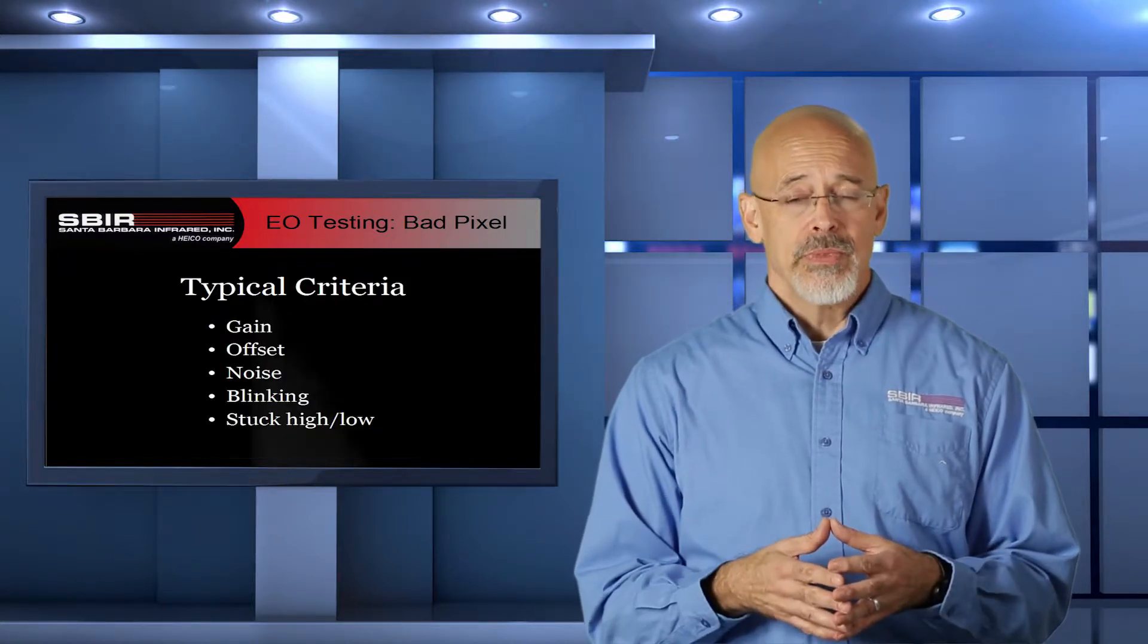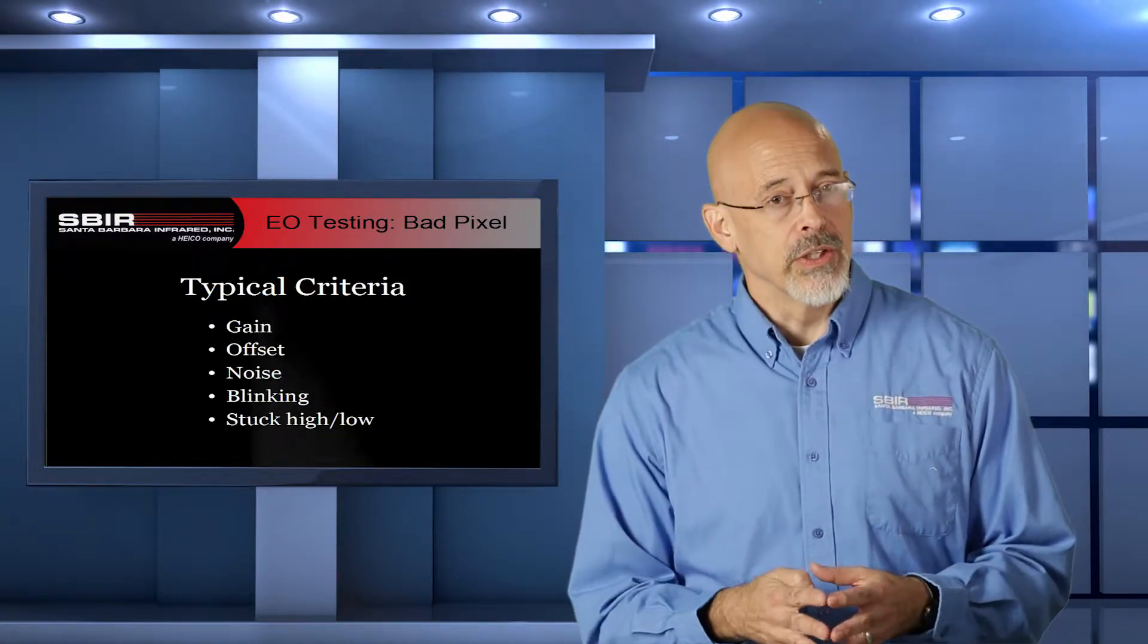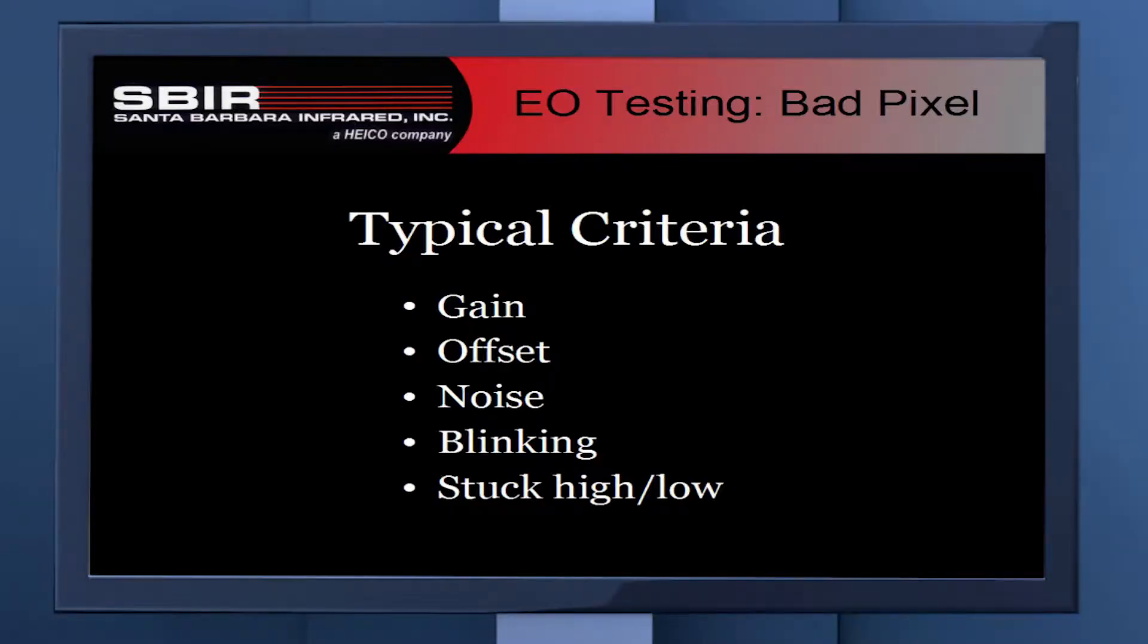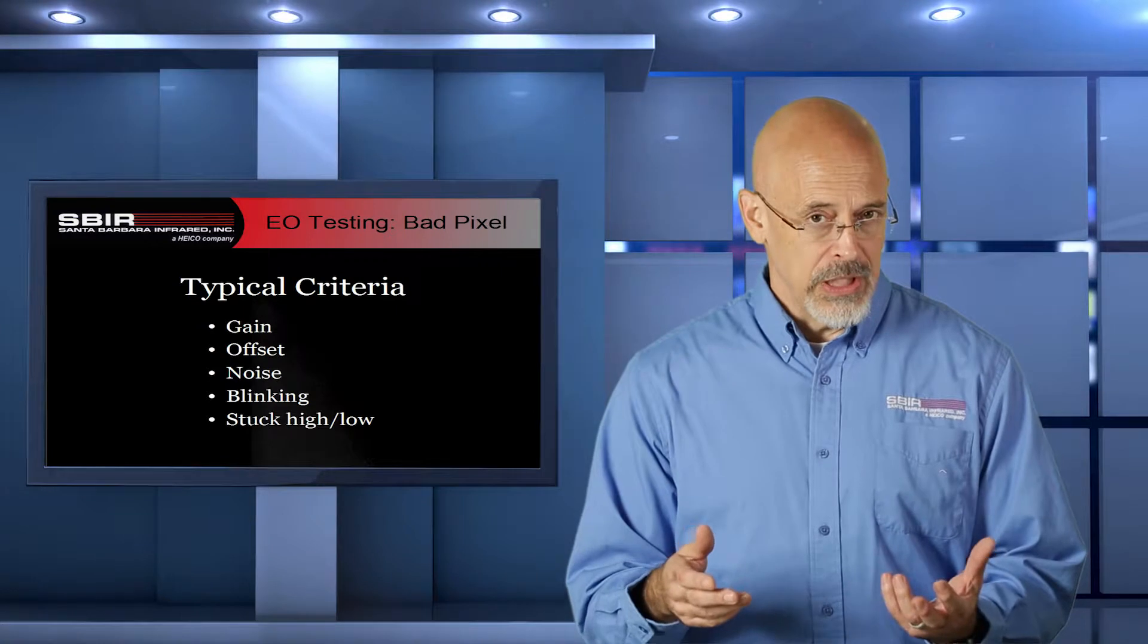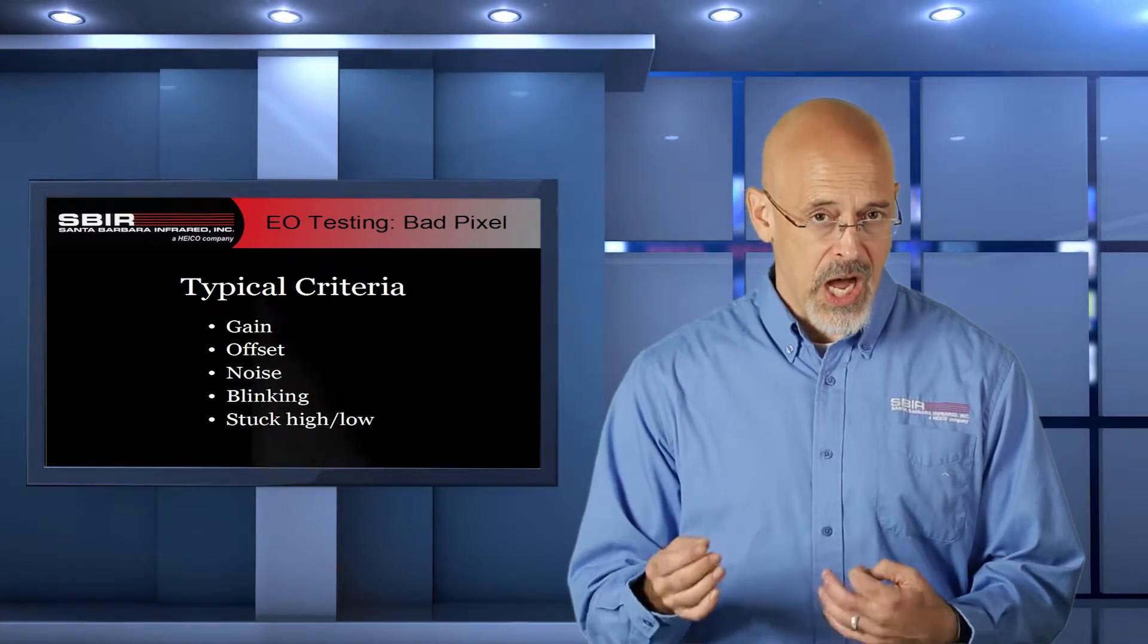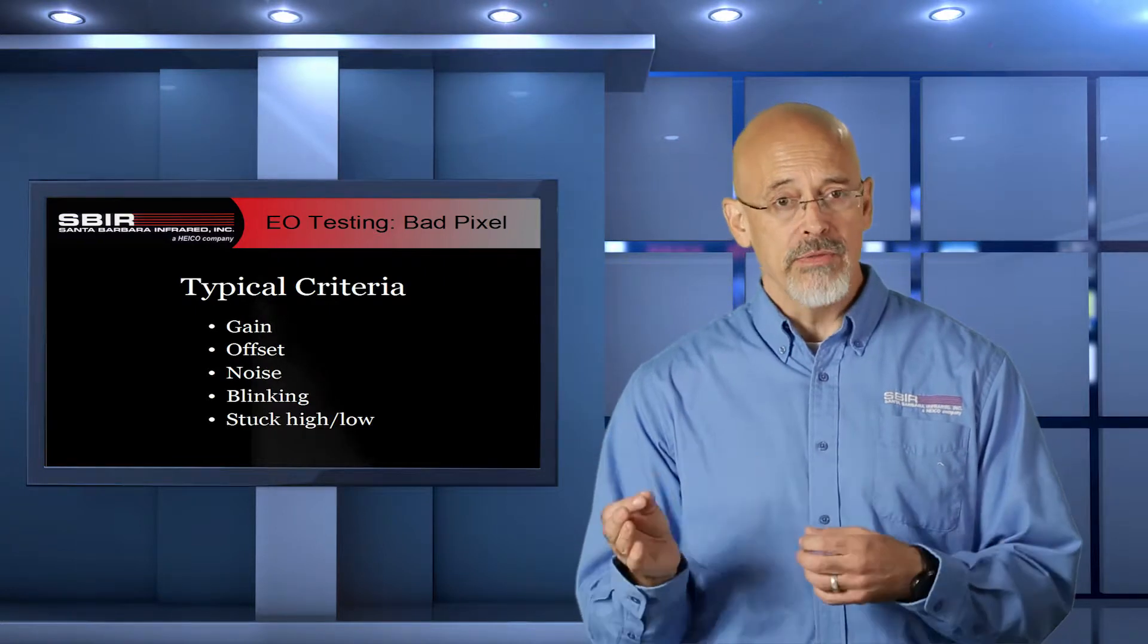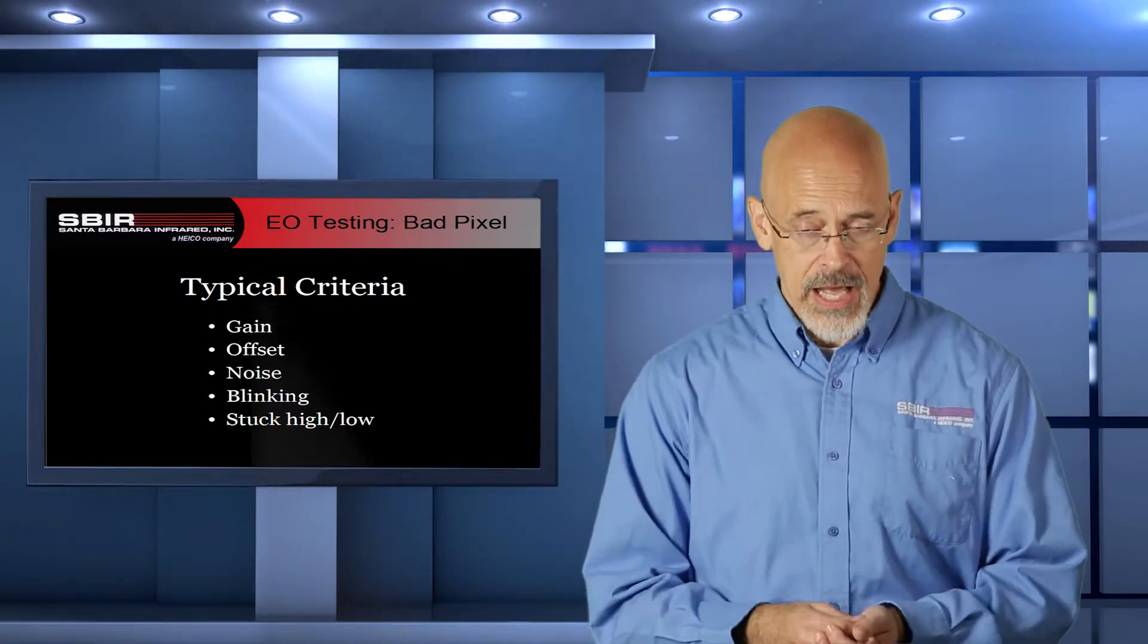So how do we determine a bad pixel? There are four criteria that are typically used for bad pixel analysis: the gain on that pixel, the offset for that pixel, noise on the pixel, and whether or not the pixel blinks. Additionally, you can determine whether a pixel is stuck high or low, and that may be in your specification, but really that's just a part of the other criteria and comes out of that analysis.